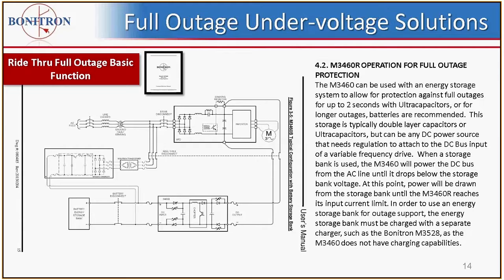So as you can see, this is the schematic. The AC line is now tied to an isolation transformer, which feeds the charger, and the charger charges the energy storage, and in this case we're looking at a battery energy storage bank. And the voltage regulator will pull from the battery energy storage bank. That's why sometimes it gets a little confusing, because internal to Bonitron we call this DC ride-through, and we call the sag ride-through AC ride-through, because of the way the power is sourced, or the energy sourced from whatever energy storage we're using.